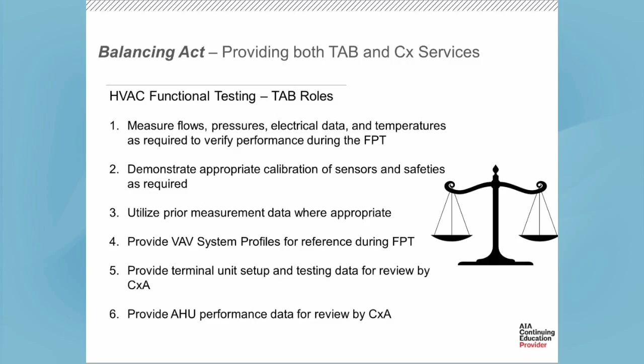So what I argue is, regardless of who the roles are, and especially if they're within the same firm, you don't want to overlap testing that has been done previously. So if these things have already been checked, if they've already been demonstrated previously, you don't do it again just for the purposes of demonstrating it during the functional performance test. But you do have to make sure that it was checked and shown to the appropriate parties at some point in time. Demonstrating calibration of sensors and safeties if needed. And then just being there to support anything else with their data, such as VAV system profiles, terminal unit setups, especially if you see some issues and things like that, and providing performance data so that the commissioning provider can back up and say, yes, this system is working as intended and to meet the owner's project requirements.